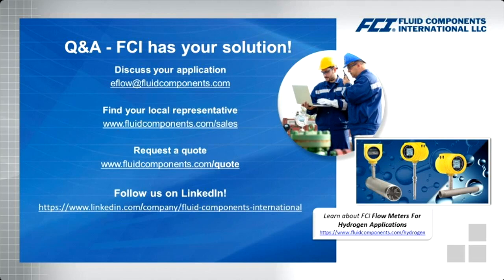Absolutely. So saturated gas is a difficult thing to measure, just for the simple fact that water itself has a really high thermal conductivity rate, and it causes problems with most sensors. So we have a specific sensor. We have a wet gas sensor that's specifically designed for really wet applications. It has a little screen filter media that it forces the gas across, and as it's passing through that filter media, it drops out that high liquid content and then flows the gas across those sensors. Definitely, we can make those measurements.